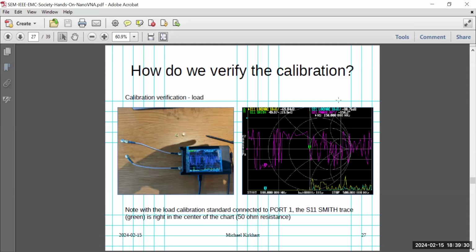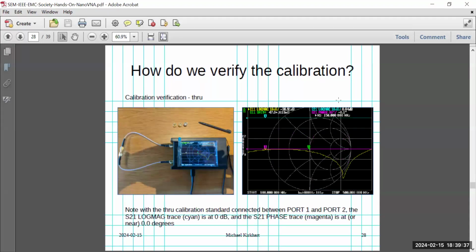Okay, we good with that? We just have one more check to do, and this involves using that through connection. We probably should have done this first because we already had it there, but whatever. Get used to this. If you're using a regular VNA without an eCal module, you're going to get used to swapping calibration standards all the time. Yes, this is your life. It's like, okay, I spend 10 minutes calibrating and 30 seconds doing my measurement. But that's the way. If you're doing tests, everybody knows most of the time is the test setup. Once you get the test setup there, you do your test and it's over within 5 minutes, but it takes you 4 hours to do the setup. Situation normal.